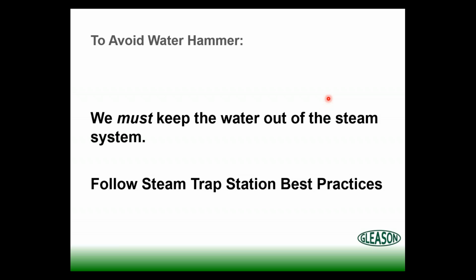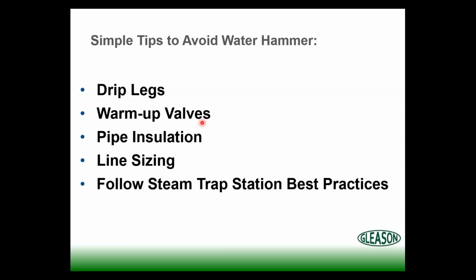So to avoid a water hammer, we got to keep the water out of the system. Okay, so we got to follow our steam trap best practices. Let's put in the appropriate number of properly sized drip legs where they should be. Warm-up valves around any large bore, anything 3 inches or greater, steam system isolation valves. Please make sure our pipes remain insulated, and then we need to follow our steam trap station best practices.